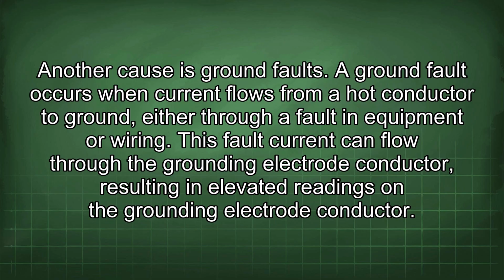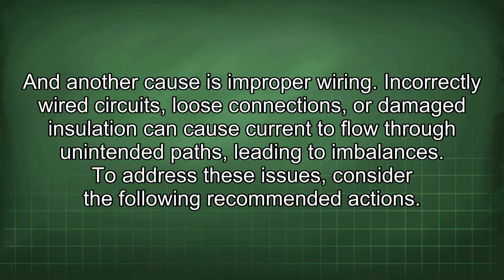Another cause is ground faults. A ground fault occurs when current flows from a hot conductor to ground, either through a fault in equipment or wiring. This fault current can flow through the grounding electrode conductor, resulting in elevated readings on the grounding electrode conductor. And another cause is improper wiring. Incorrectly wired circuits, loose connections, or damaged insulation can cause current to flow through unintended paths, leading to imbalances.